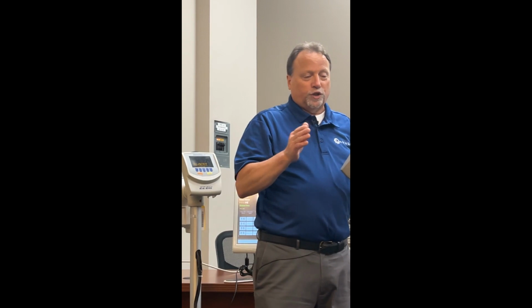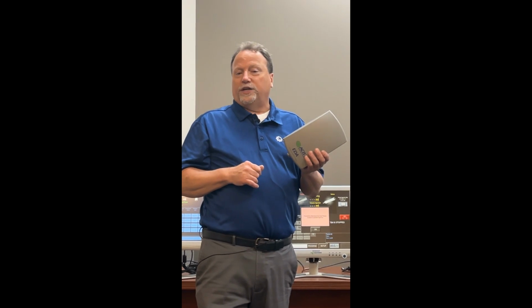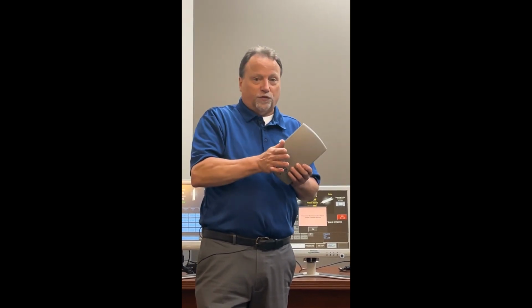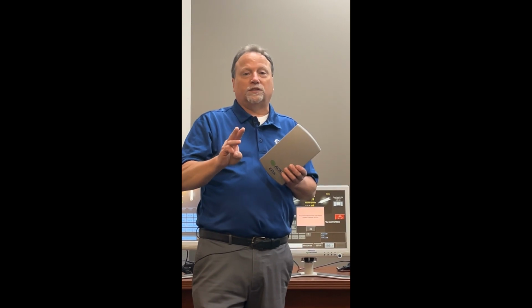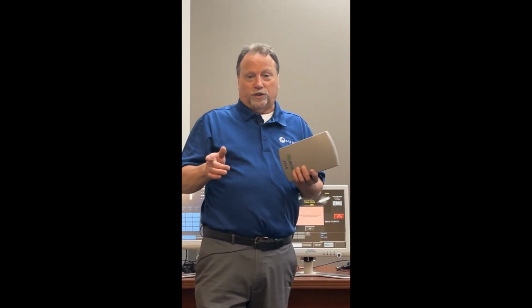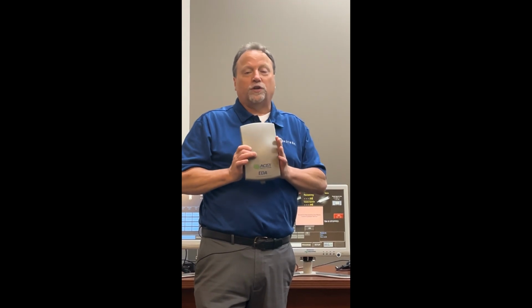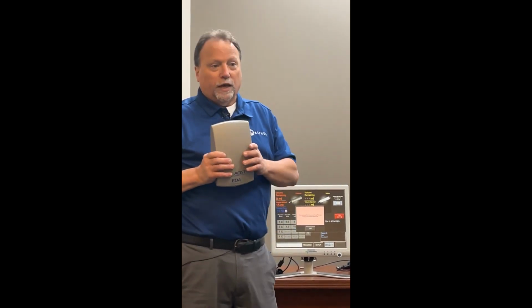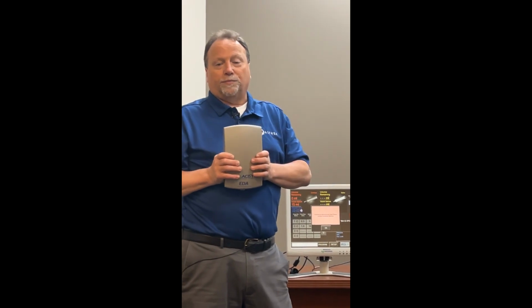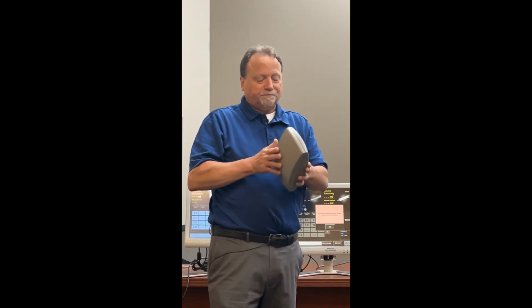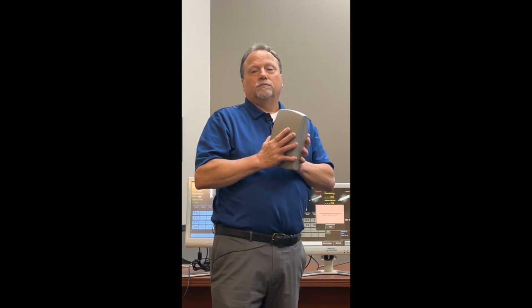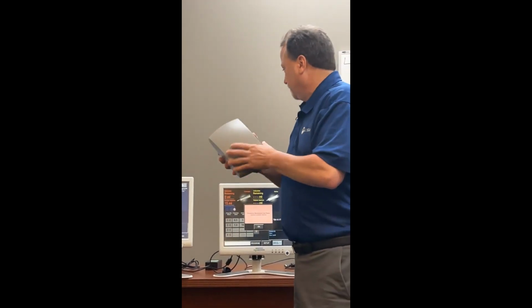There's two different forms of PMs that they do out there. One's a PM and one's a field test form. On the PM, all you do is basically unplug it, it tells you that it's out of range, and plug it back in. If you do the field test form, it has you do 3 different resistances to show 1 in range and 2 out of range. That has to be done so you know that your EDA module is calibrated properly. And we can calibrate these here at depot level at Althea. So we do make that module, or that test jig, to use on this. It's included in our Acist service kit.